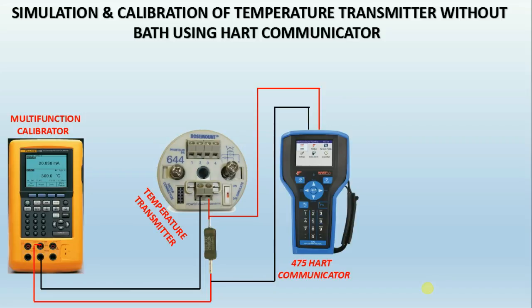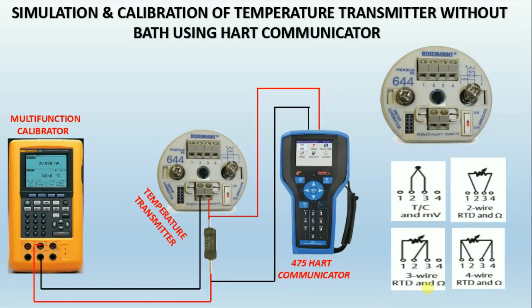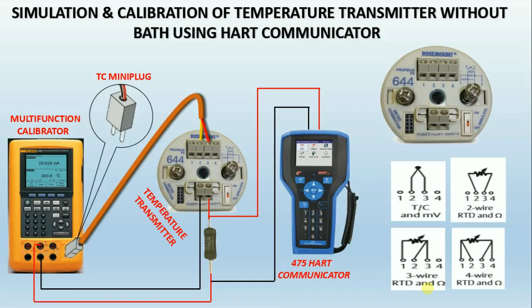The transmitter can be configured for different types of RTDs and thermocouples, and shown how to connect to the transmitter according to your configuration. Here as an example, I connected the thermocouple option in the transmitter for calibration. Before simulating, first select the source in the process calibrator, then press the TC/RTD button and select the type of thermocouple. Then simulate temperature by feeding through the keypad. Before calibrating, the transmitter has to be configured to thermocouple K-type by using the HART communicator. This process calibrator can be used for sourcing temperature according to your range, and it can also measure loop milliamps according to the temperature you are sourcing.